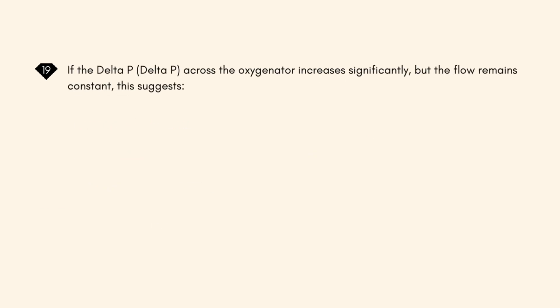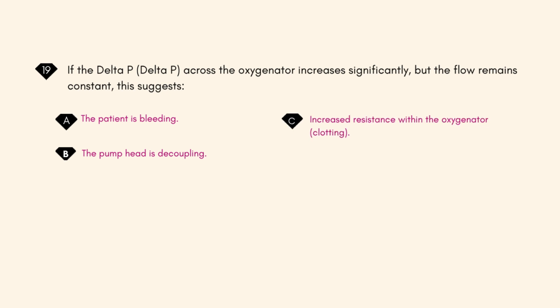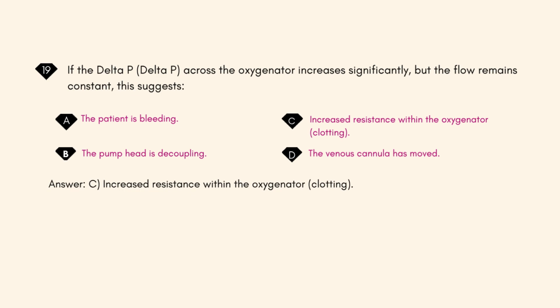If the delta P across the oxygenator increases significantly, but the flow remains constant, this suggests: A. The patient is bleeding. B. The pump head is decoupling. C. Increased resistance within the oxygenator, clotting. D. The venous cannula has moved. Answer: C. Increased resistance within the oxygenator, clotting.